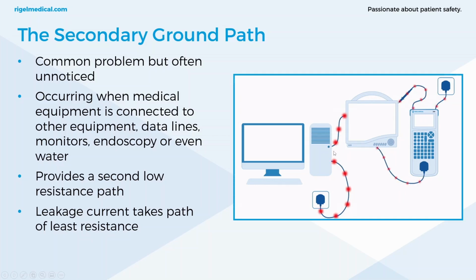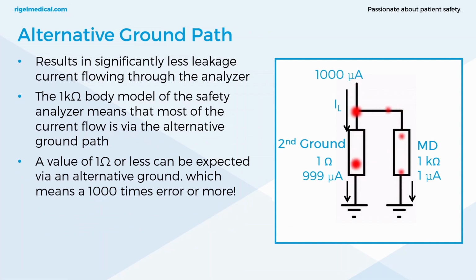Most of the current is taking the path of least resistance rather than through the measurement of the safety analyzer. So the safety analyzer uses a body model, which is typically 1 kilo ohm. It's going to follow that easy path back to earth, or back to ground, via the data lines. This results in significantly less current flowing through the analyzer, which is potentially dangerous because hazardous equipment could pass the leakage test.